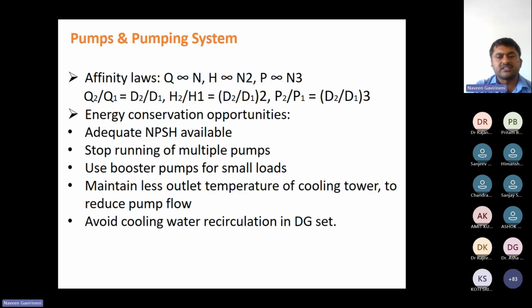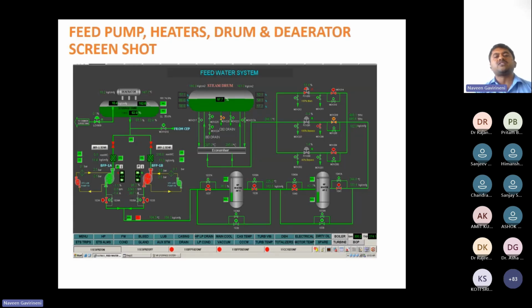Avoid cooling water circulation in the DG sets. DG sets designed for air cooling are sufficient. But earlier, our DG sets were designed for the feed water system only. So you just see the screenshot. This is the pump arrangement.